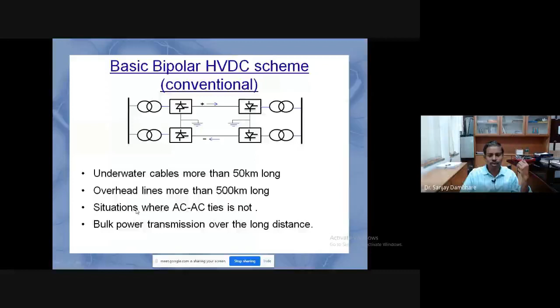When you have an HVDC link embedded in a conventional AC system, this HVDC link can control the power over this transmission line, and it can also control the power over the AC line, because some of this power is being transferred from this area to that area. The HVDC link, when embedded in the existing power system, is used for interconnecting two systems of different frequencies and bulk power transmission, but it also facilitates the power system engineer to control the power flow.